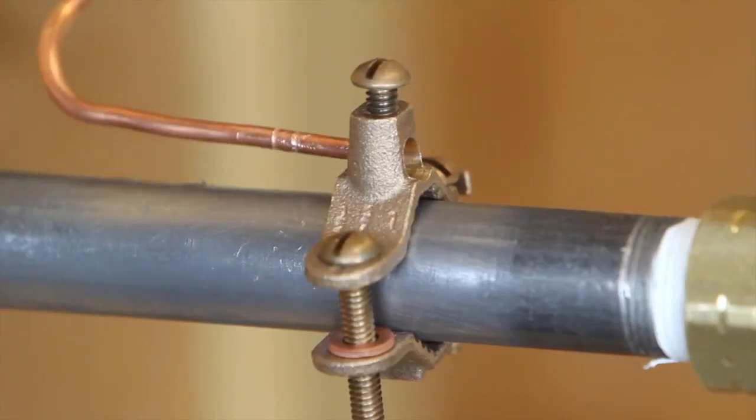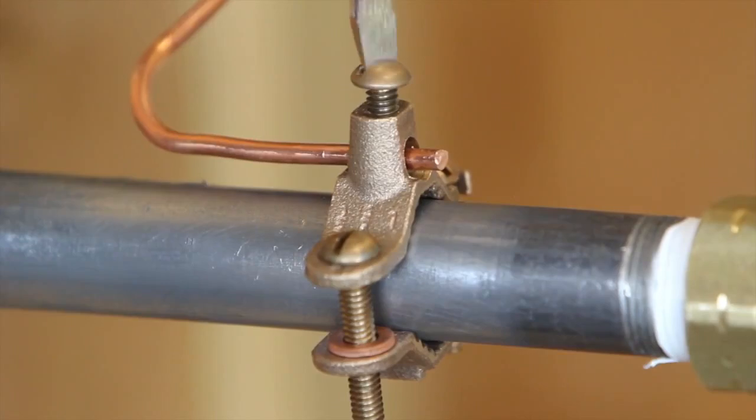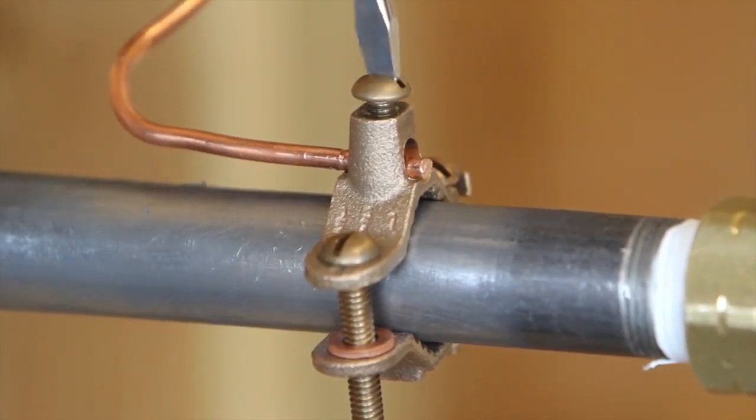Then run the minimum 6 gauge copper wire through the bonding clamp. This wire is then attached to the home's grounding network via the grounding bus bar in the panel box.